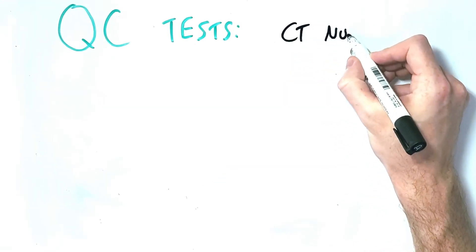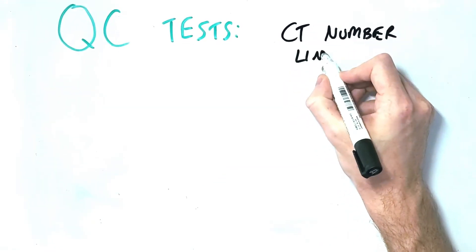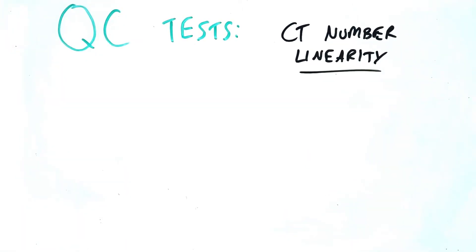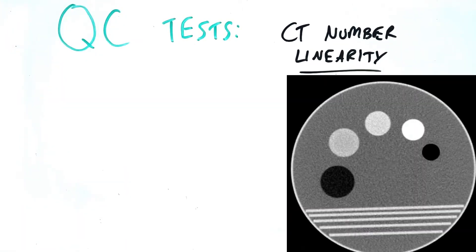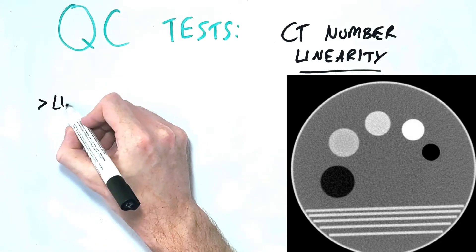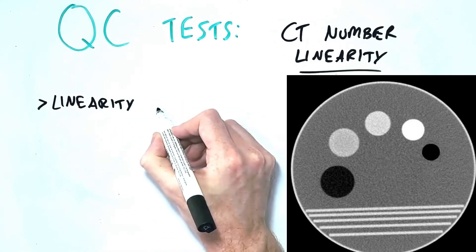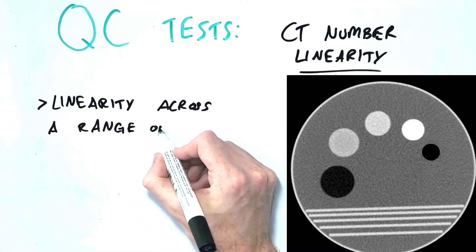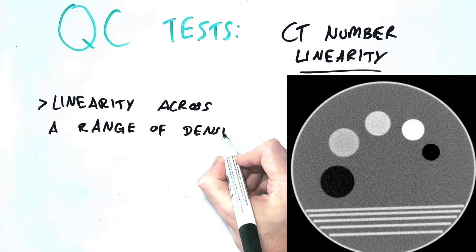CT number linearity refers to the response in measured CT numbers to changes in the type of material or tissue being scanned. A phantom with areas of various density simulating air, fat, water, soft tissue and bone is scanned and then the measured Hounsfield units are assessed and compared to the values they should actually represent based on their known linear attenuation coefficients. This allows us to assess if the scanner is properly detecting changes across a range of densities.